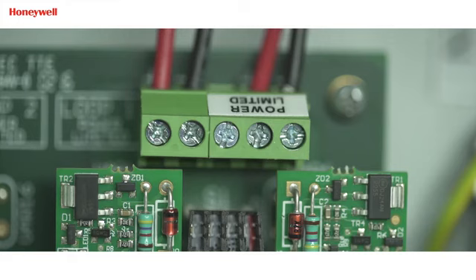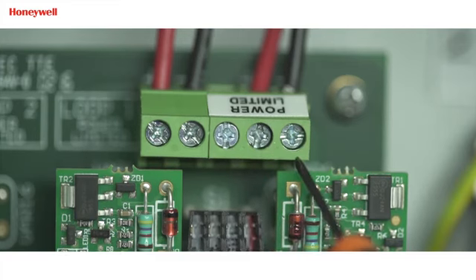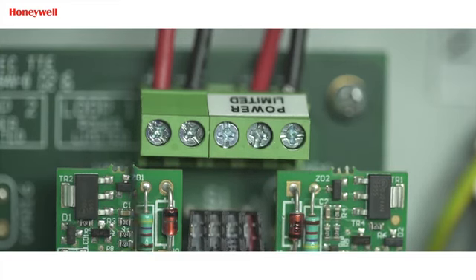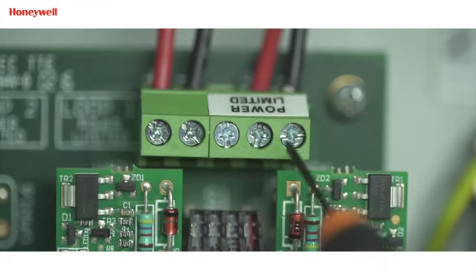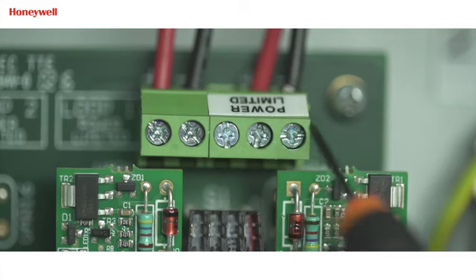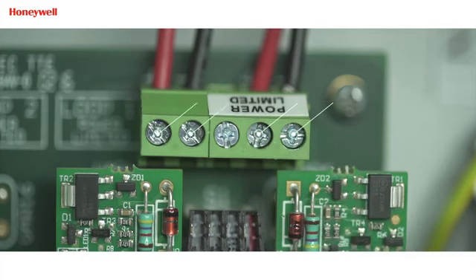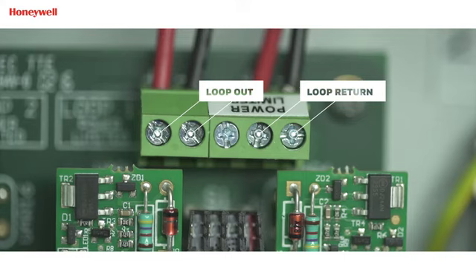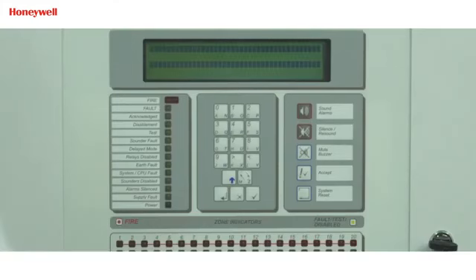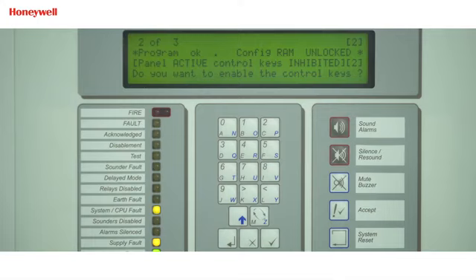TB1 is a 5-pin terminal: plus, minus, E, plus and minus. Left side plus and minus is loop output terminal. E is earth terminal for loop, and right side plus minus is loop input terminal. We need to connect loop output and input of field wiring on the respective terminal. Once all the connections are done, power on the panel, and now we must perform the setup process.